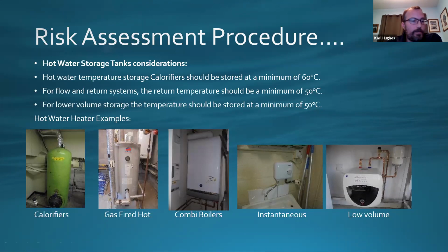One of the things there is the cold water comes in at the bottom of it, comes out the top of it. So one of the things you need to make sure is the water coming out of that cylinder is set to a minimum of 60 degrees. As we said previously, Legionella bacteria won't grow in water greater than 60 degrees. If it's got a flow and return system on, which you'll see in a lot of modern buildings or larger buildings where the water goes round and it's got a circulation pump that will bring the water back to the cylinder, the water coming back to the cylinder needs to be a minimum of 50 degrees.